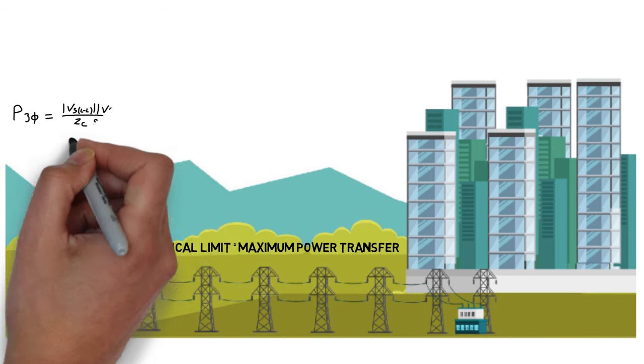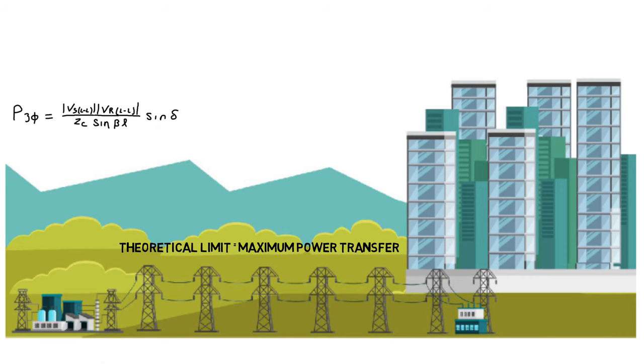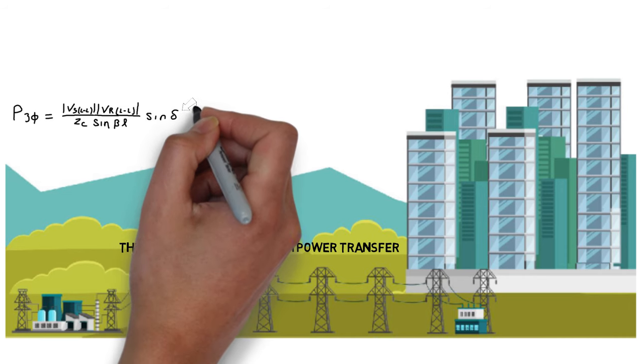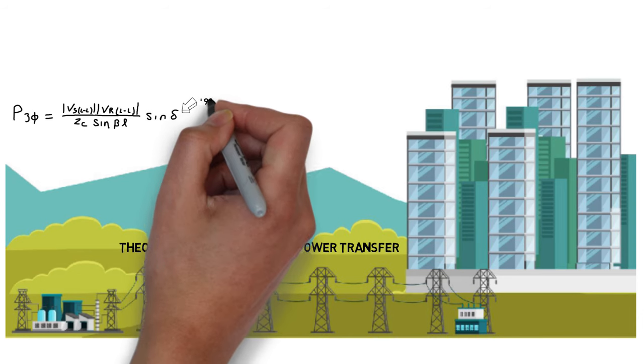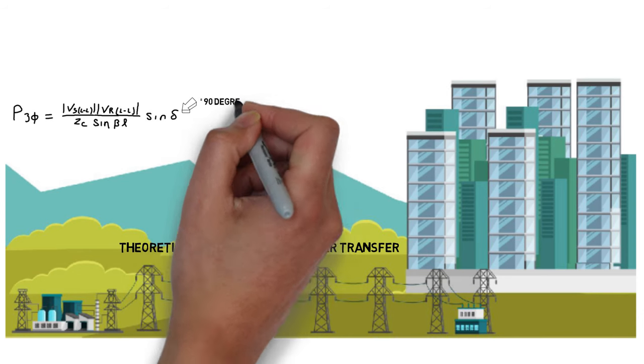The real power transfer over the transmission line is given by the theoretical limit. The maximum power that can be transmitted in steady state without compromising the stability of the line occurs when the angular displacement is equal to 90 degrees.